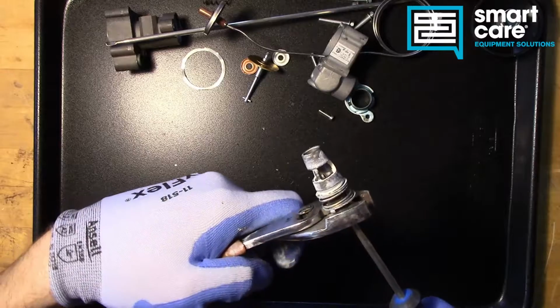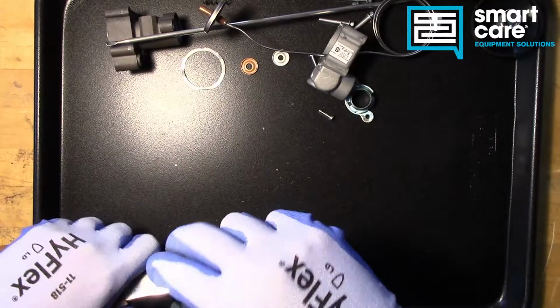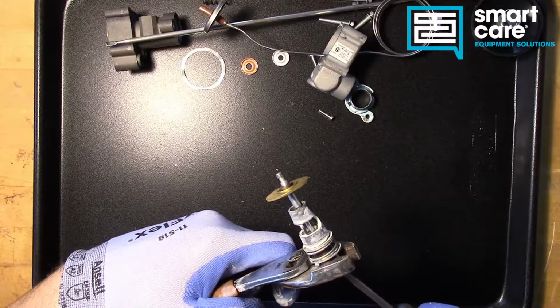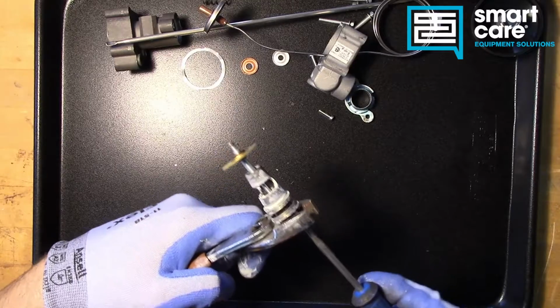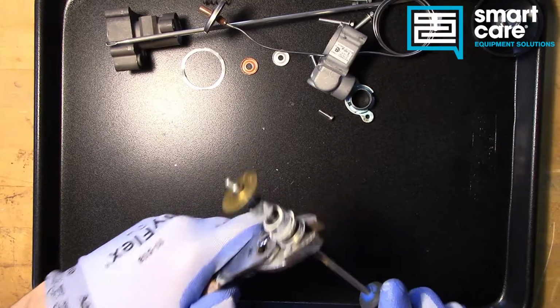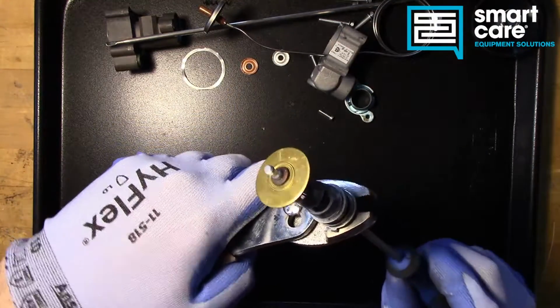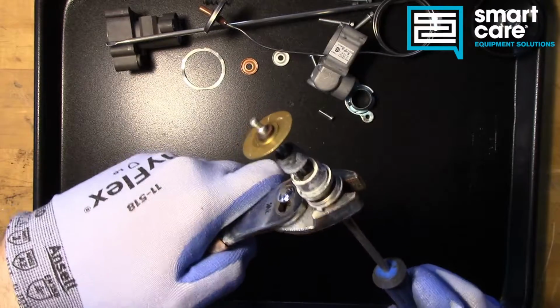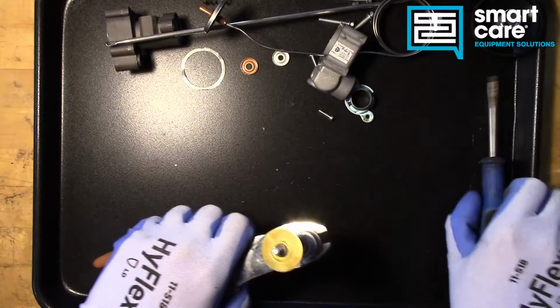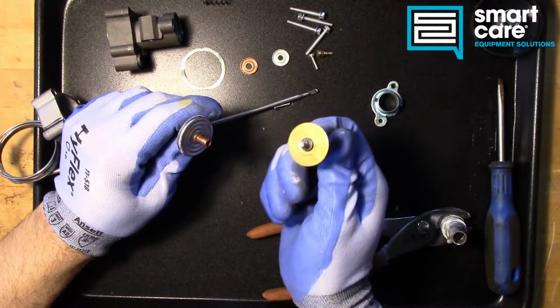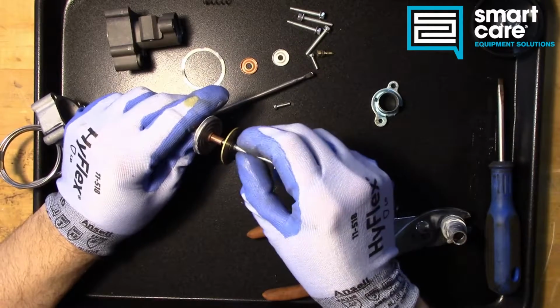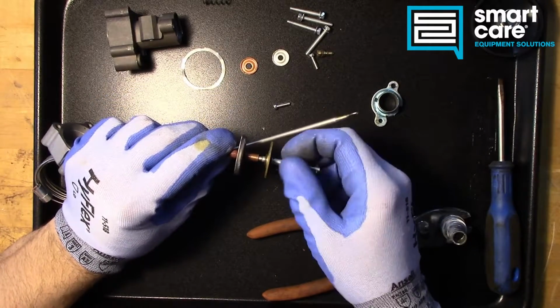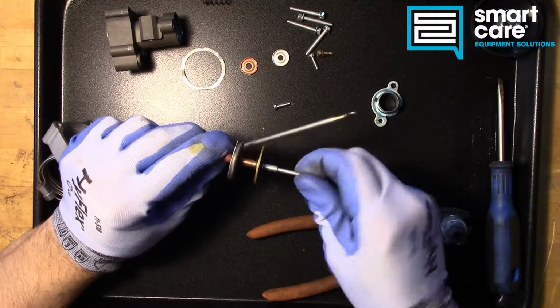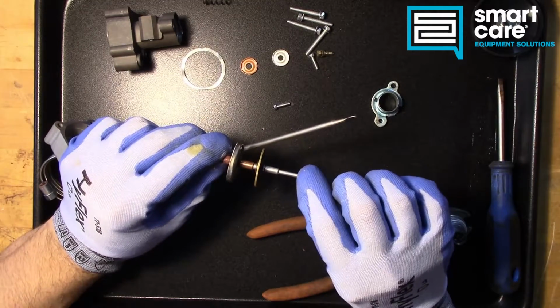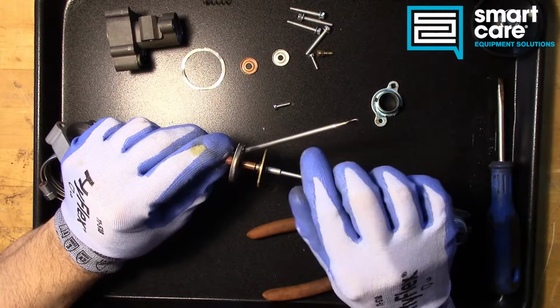If you look down inside, in fact, let me put it on like this because it might be easier to see. That T-slotted fixture down in there spins when we adjust that calibration. So that's all they're doing. When you adjust the calibration, what you're actually doing is changing how far this seal plate is threaded into this bellows. You see they get closer together and further apart as you thread them in and out of each other. So when you make an adjustment to that screw down inside there, all you're doing is changing the precise position of this plate in relation to this bellows.